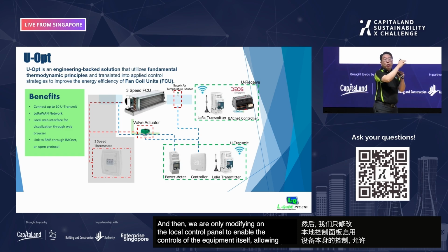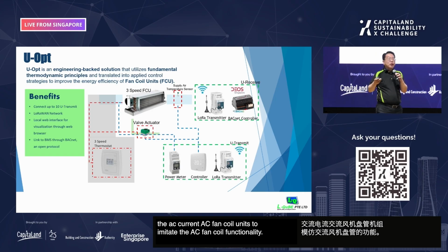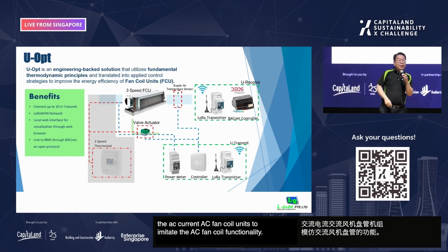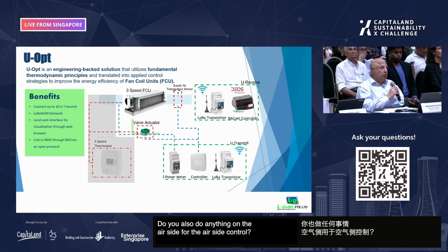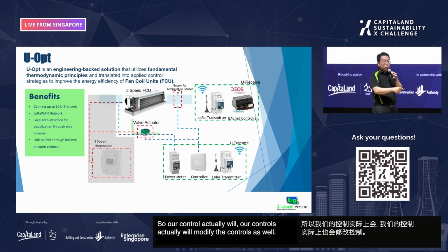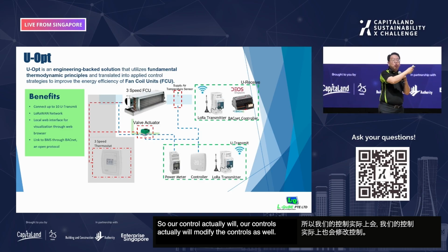And then we're only modifying the local control panel to enable the controls of the equipment itself, allowing the current AC fan coil units to imitate the EC fan coil functionality. Okay. Do you also do anything on the air side? For the air side control, do you do anything? Sorry, so our controls actually will modify the controls as well.